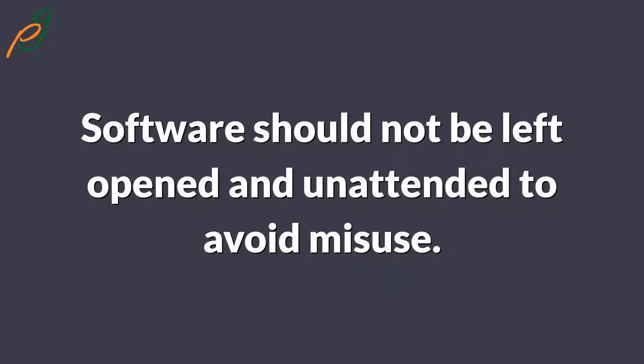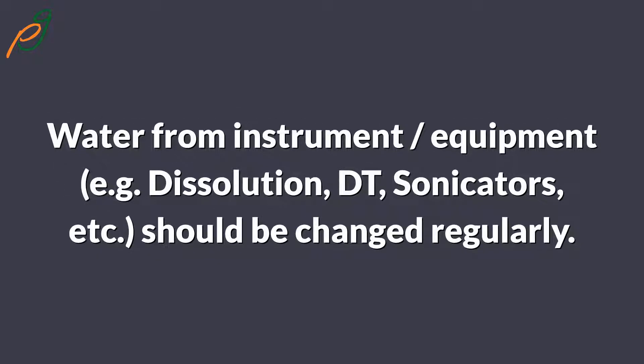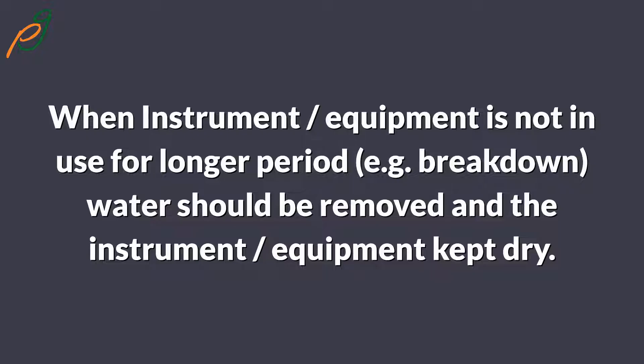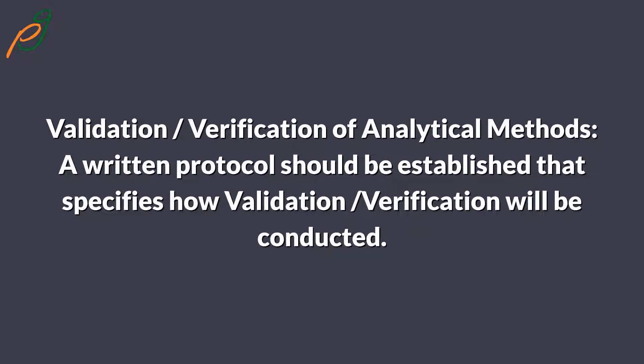Software should not be left open and unattended to avoid misuse. After use, save the data and close all operating systems properly, then switch off the computer. Water from instruments and equipment — e.g., dissolution testers, sonicators, etc. — should be changed regularly. When instrument equipment is not in use for a longer period, such as during a breakdown, water should be removed and the instrument kept dry.